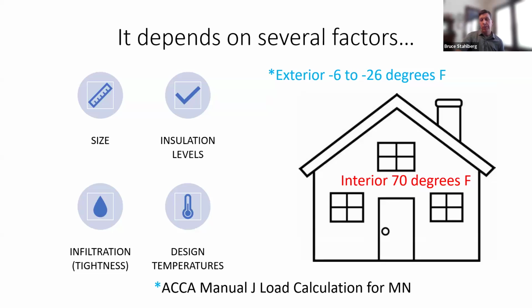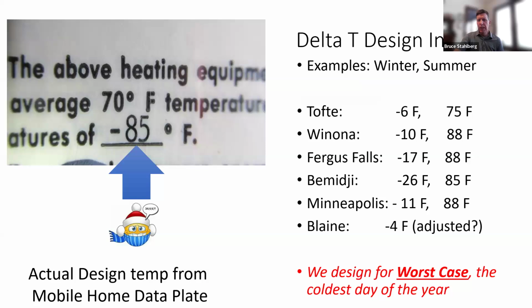Now, that number, the amount of the load, is dependent on a lot of different things. The square footage or the size, how much insulation we have, how tight it is with infiltration, and then what is our design temperature. Now, for example, we often use 70 degrees, and this is for heating, on the interior temperature, and say we want to keep it around 70 degrees. The exterior temperature, which we don't have control over, can vary from town to town. And the next slide shows all the different towns in Minnesota and the various winter and summer design temperatures.